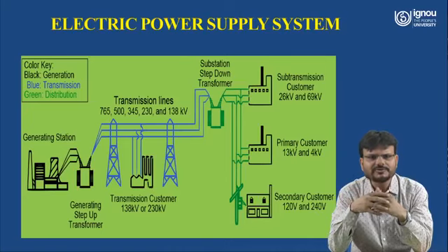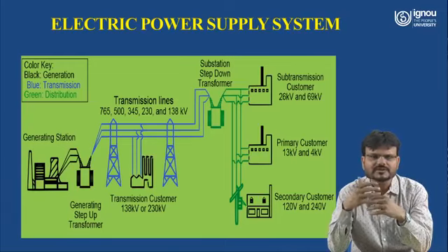So what we will do is use a generating step-up transformer, where this 11 kV has to be converted into either 132 kV, 220 kV, or 765 kV, depending on the type of generating station and the amount of power being generated from that particular power plant. Now, what is the use of this high voltage transmission?